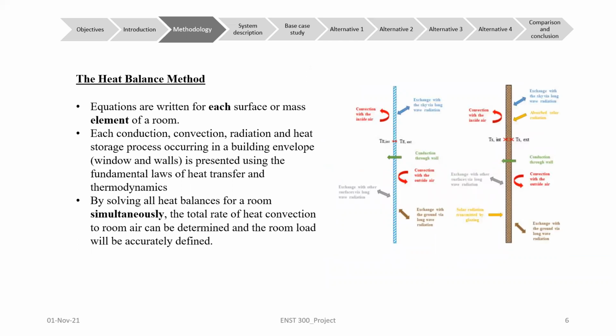Based on what was said, it is primordial to calculate the cooling load of the buildings. So the most known method for calculating the building load is the heat balance method. This method is based on the finite volume approach. It consists in discretizing the walls into finite control volumes and applying the heat balance equation on each of them. But for simplification, the heat flux is sometimes assumed to be unidirectional along the thickness of the wall in order to get a 1D element.